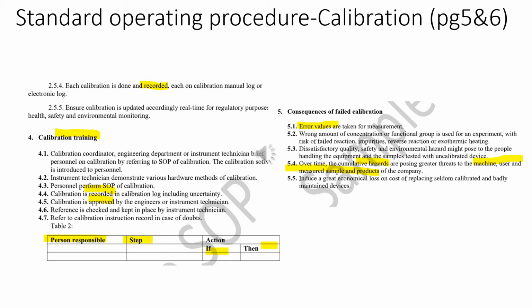The error values are also taken, and it is important to carry out calibration as written down here to remove any hazards that can be cumulative over time and might pose threats to the machine user, to the measured samples, and to the data. The error might be carried on and cause bad consequences to the user. So it is good to avoid this kind of thing.